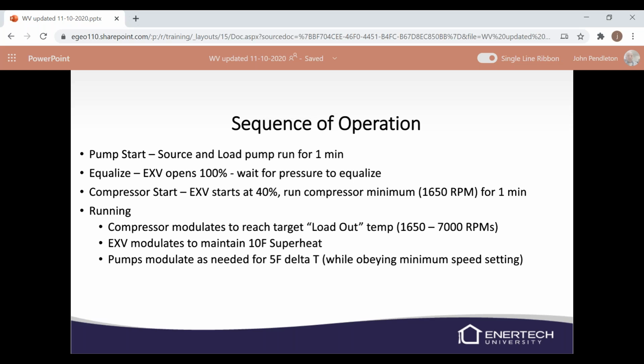Then the compressor will say running or heating call. The compressor is going to modulate to reach its target load out temperature, and it'll show an RPM range on the screen of its target range. And then the expansion valve is going to modulate, and it tries to maintain 10 degrees of superheat. Then the pumps will modulate on their own to try to maintain your 5-degree temperature difference while still obeying your minimum pump speed. So if your minimum pump speed is at 25%, you're running at 25%, and you're at a 3-degree temperature difference, it's not going to slow your pumps down any farther than that 25%. That's just how it's set up there.